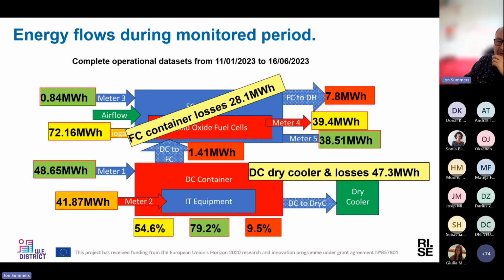In terms of the heat, 1.4 megawatt hours of that 41 megawatt hours was recovered to preheat the incoming air to the fuel cell container. And from the fuel cell container, 7.8 megawatt hours managed to enter the building for space heating. And so we were recovering about 9.5% of the energy if you work out the gas as the prime source of energy. It's the sum of these two, because we were pulling 0.84 megawatt hours off the grid for the fuel cell container, and we were putting 72 megawatt hours of gas into the container. So 7.8 megawatt hours was used as heat recovery.